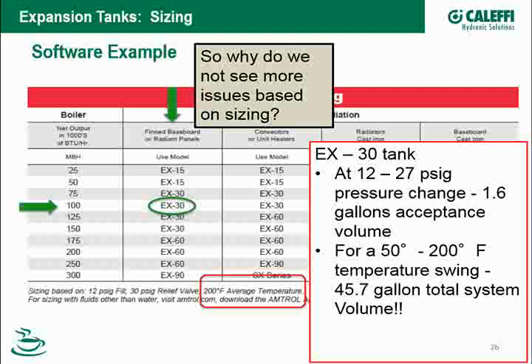I discovered that one of the manufacturers' websites, when you size, especially for a large system like that, will give you the compression tank size as well as a diaphragm or bladder tank size. And the example I did for a customer that was doing 2,000 gallons worth of water, it went from like a 150 gallon bladder type tank to 383 gallons of just a plain steel compression tank. So it's a huge difference. So just be aware of that.